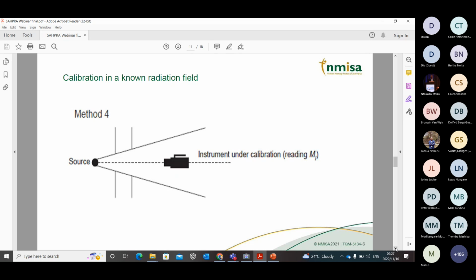And this source has been characterized by using a dosimetric method to ensure that the amount that we say it is giving is correct. And by using that method, we are actually using a calibrated standard, which is our national standard, to characterize the beam that we have. We determine at different distances the amount of dose rate, or rather the ambient dose equivalent rate, or the exposure rate that is going to be displayed as a true value. And then the unit under test, which will be the measurement instrument that is brought in, will be directly compared to what is being given off by the radiation source. Can we move to the next slide, please?